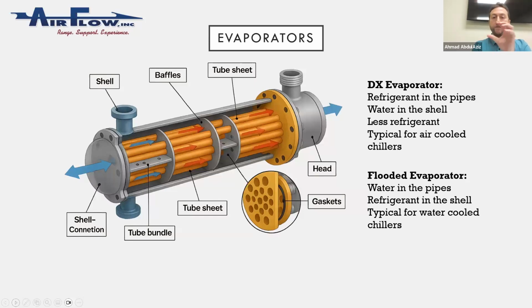DX means your refrigerant will go through your tubes. So you will get a smaller amount of refrigerant inside that shell because the refrigerant is already inside your tubes or pipes and water is surrounding it. In a flooded evaporator it is the opposite. The refrigerant is flooding around your water, which is inside your tubes in that case.